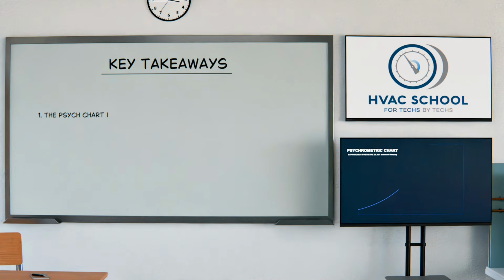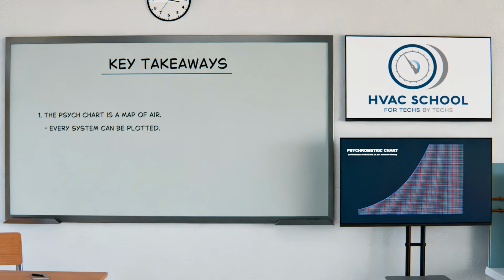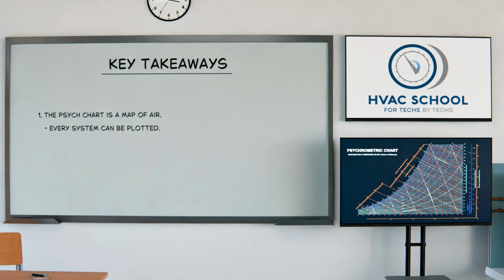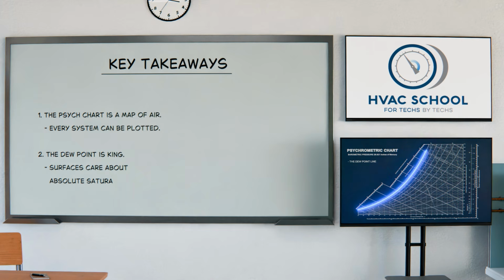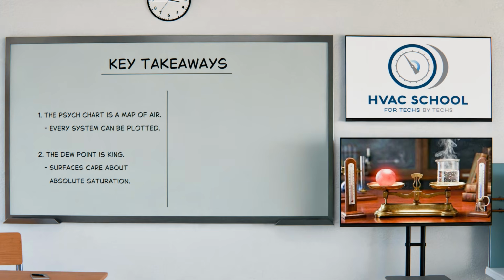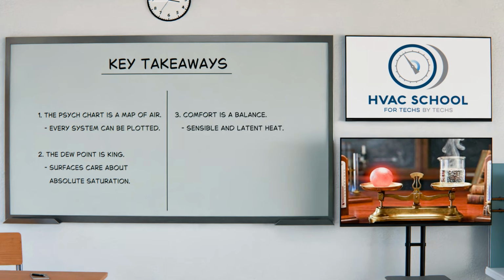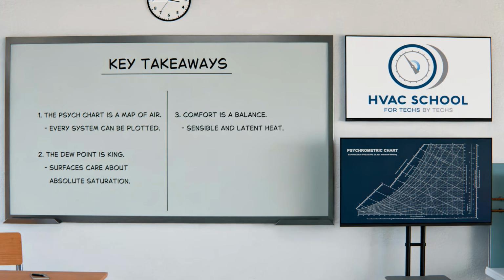So some lessons here. 1, the psych chart is a map of air's secret life. Every system you touch does something in terms of that map, if it's a forced air system. Dew point is king. Surfaces don't care about relative humidity. They care about absolute saturation. So when things start sweating, pay attention to dew point and understand it. Comfort is a balance. Sensible and latent heat both make up human comfort, as well as mean radiant effect, which we're not talking about here at all, but there's more to comfort than just the temperature on the thermostat. And understanding beats guessing. Apps are great. I love apps, but also the chart helps you to think like a psychro.